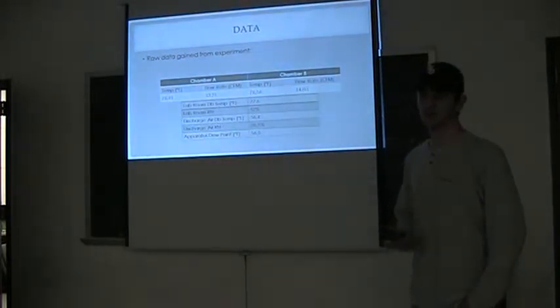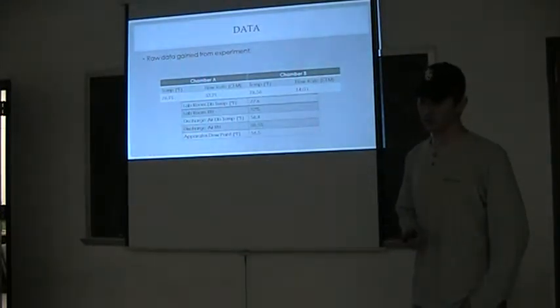This is the raw data we gained. Chamber A and B, these are the average values throughout the 60 data sets. The average temperature in chamber A was about 77 degrees Fahrenheit. Flow rate was about 33 cubic feet per minute. Chamber B was 76.5 degrees Fahrenheit with 14 cubic feet per minute.